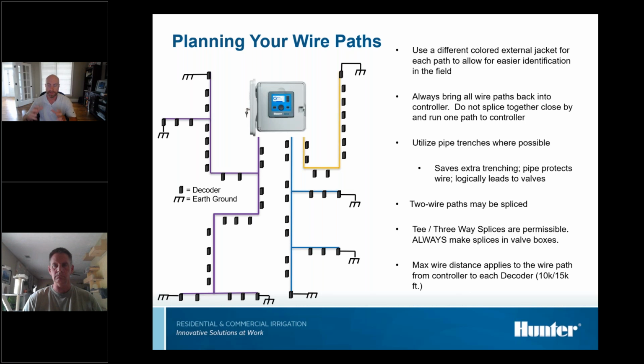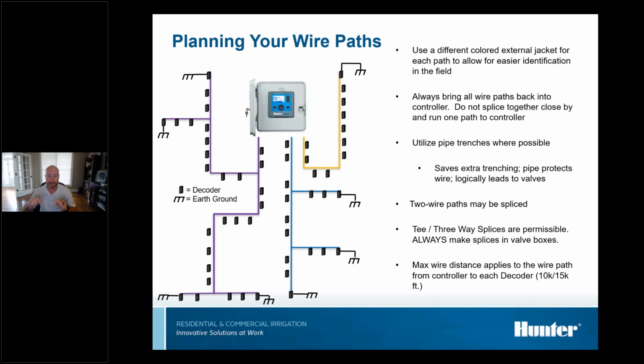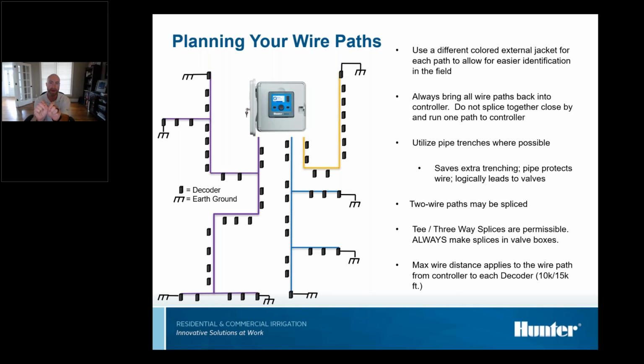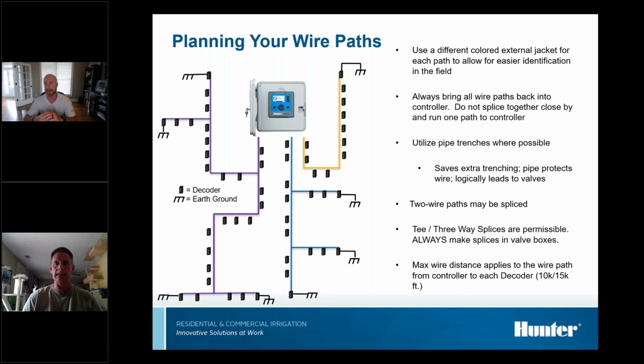Another important concept is, if you have multiple paths, always bring them all the way back into the clock. I've seen it way too many times, and this is common, especially with conventional systems, where your wire paths converge maybe 20, 50 feet from the controller, and somebody will splice them in a splice box in the ground and then run a single path up to the clock. Just go ahead and take all those paths all the way back up to the clock.